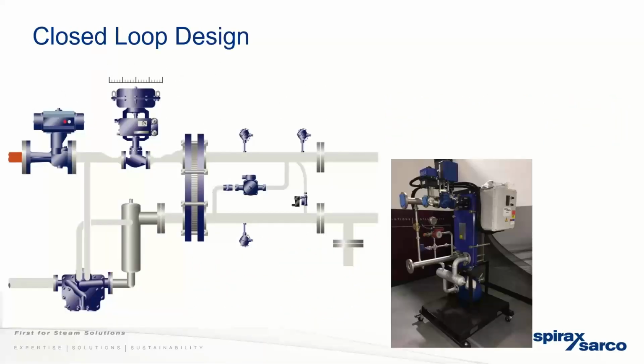So this brings us to closed loop design. A closed loop indirect heat source would be the more efficient way of heating, and it'll take away those risks of contamination with the piping and the boiler chemicals.